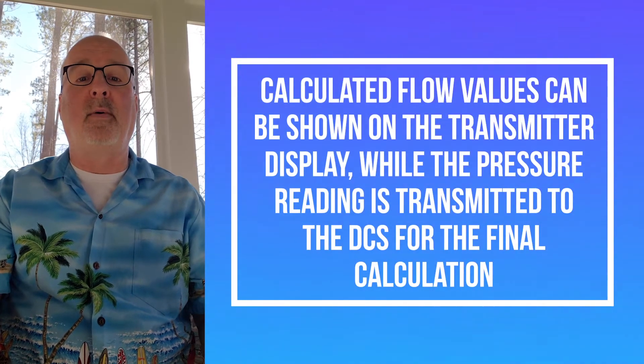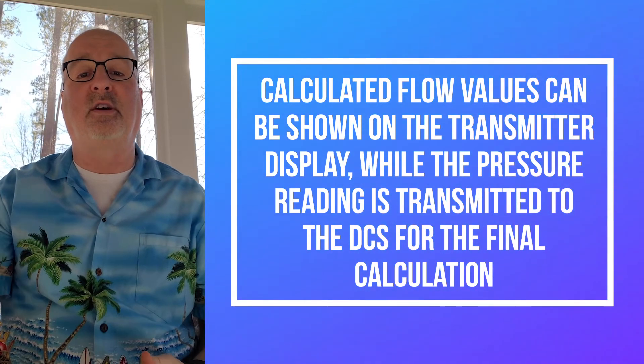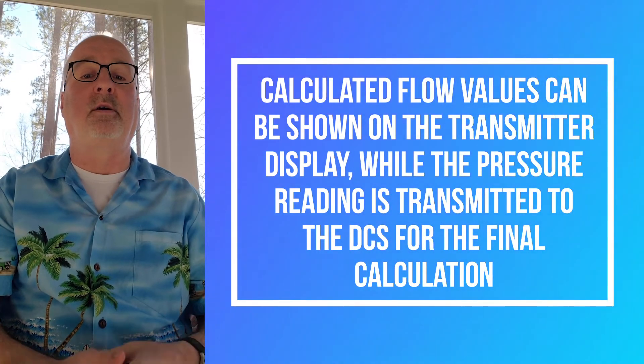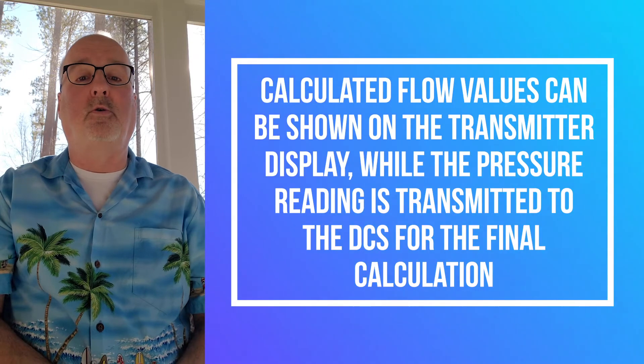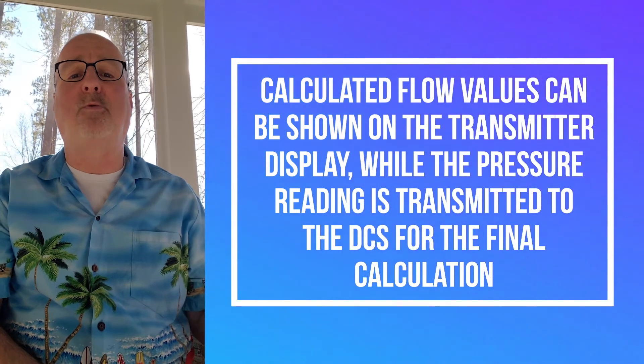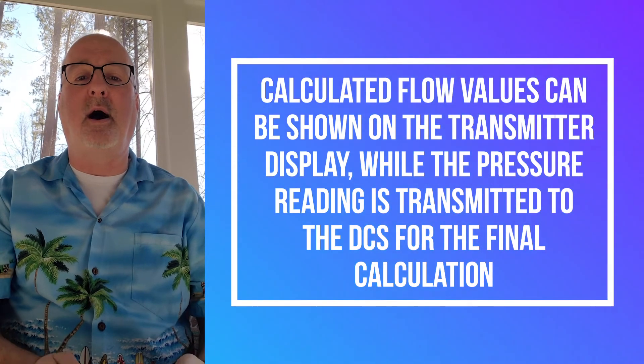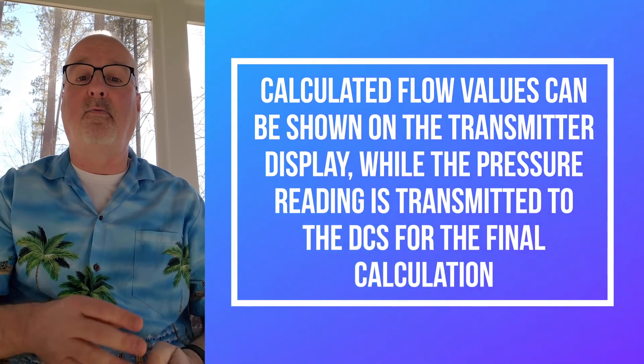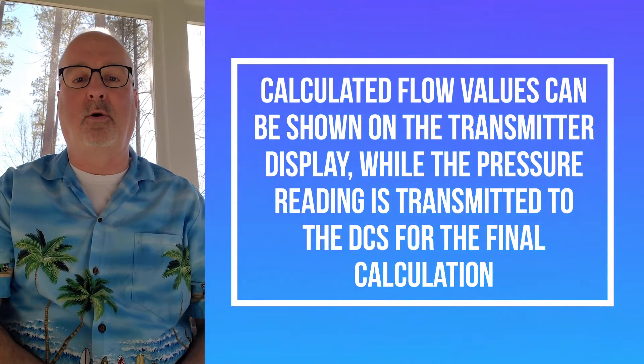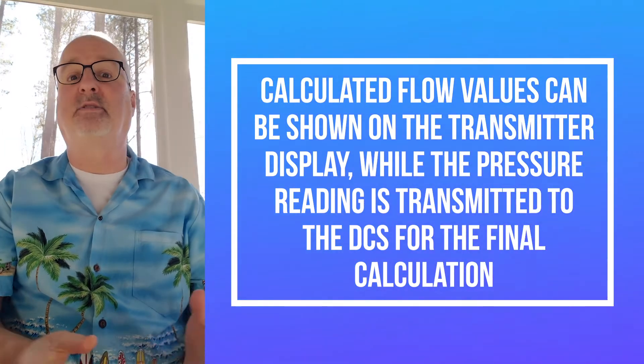Now there's one other area where you may want to use the square root function. Say you've got your transmitter measuring DP, you're sending the signal off to the DCS, and your DCS is doing all the square root evaluation. However, you have a local display, and you'd really like your technician who's out there working on the transmitter or on the process to be able to see what the flow is on the display. With Yokogawa's transmitter, you can actually set the display up to read the flow by square rooting the DP, but the actual output of the transmitter still be non-square rooted. This is important if you need this type of system.